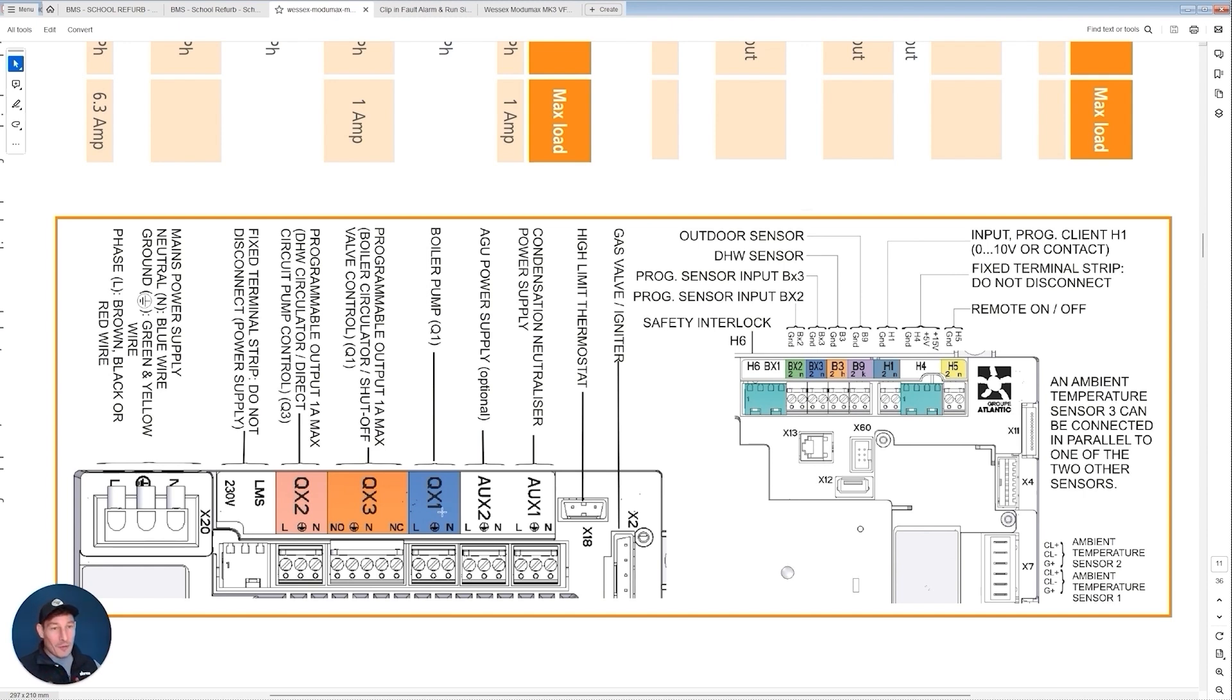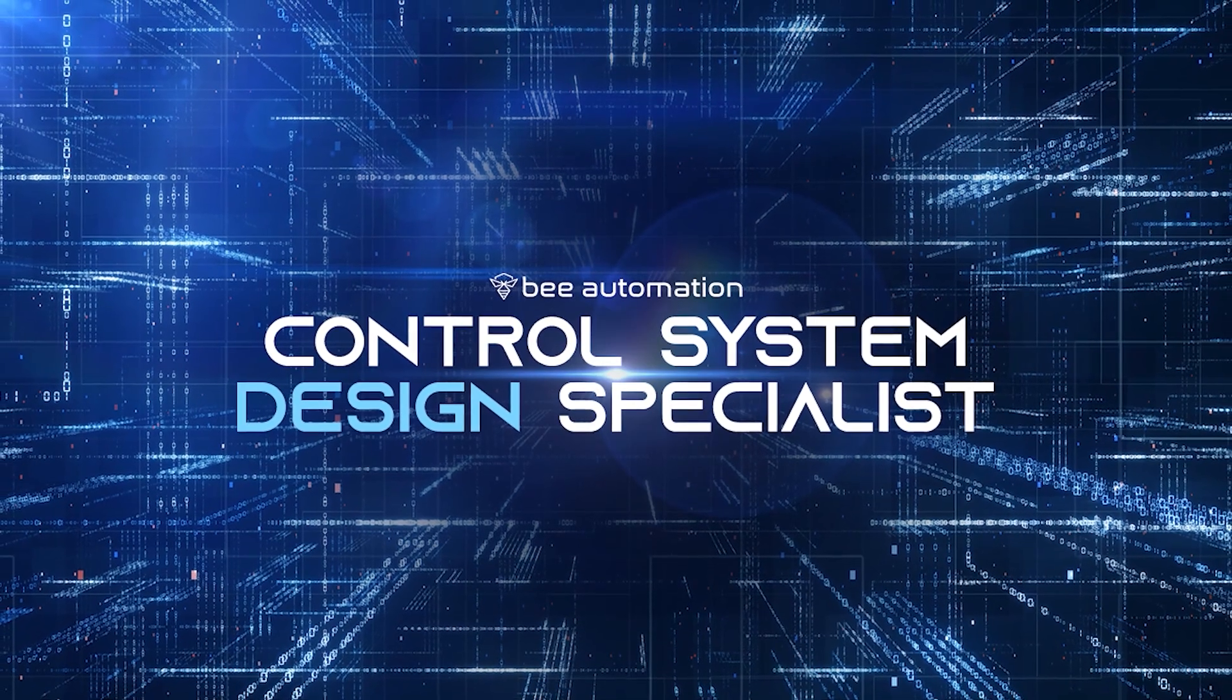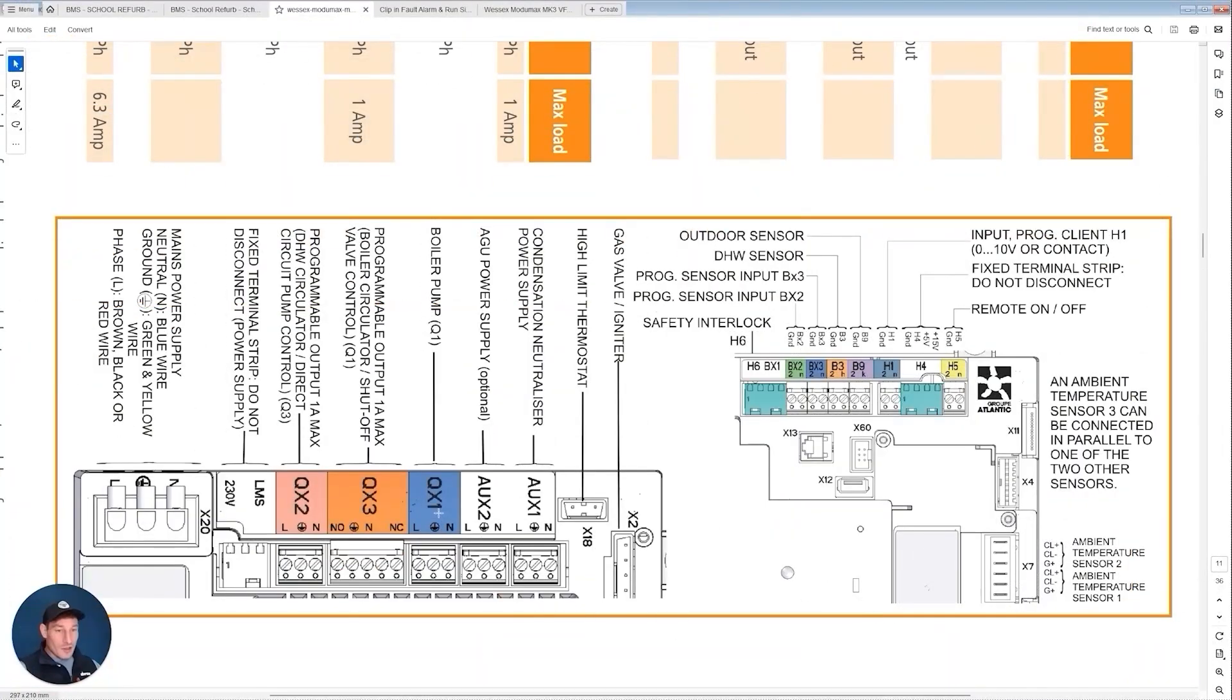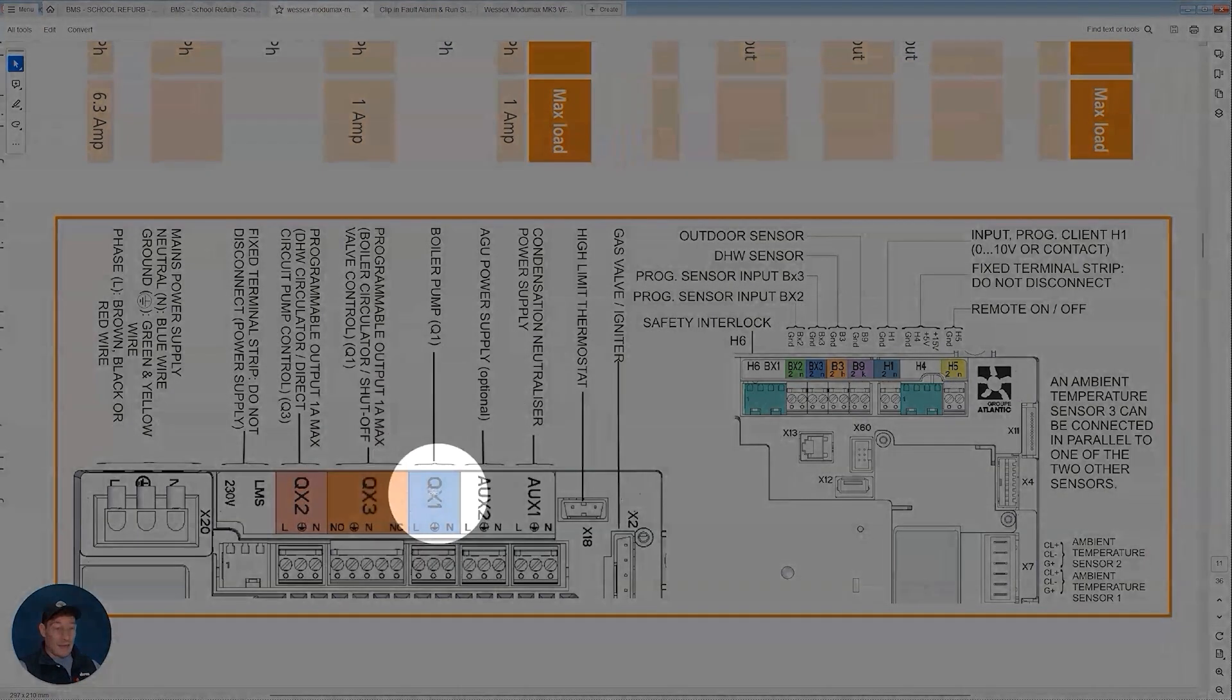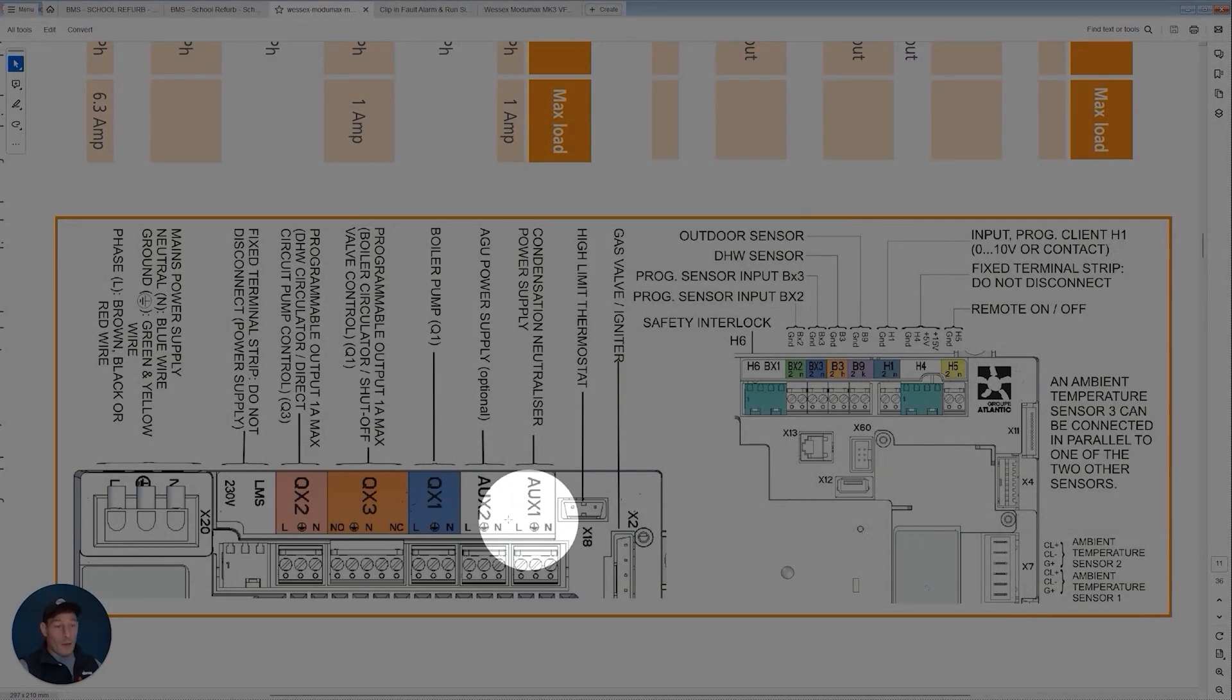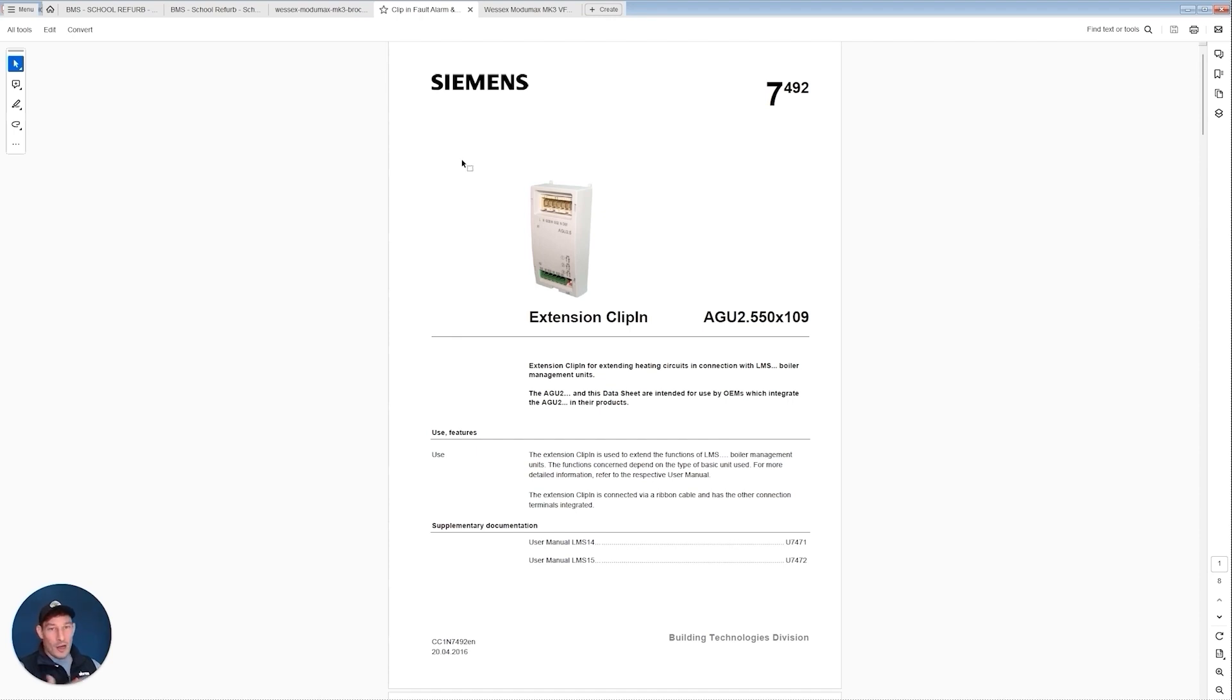We go into the details of what I'm about to go through in Control System Design Specialist, but just to quickly give you a brief overview, I had to spend a lot of time back and forth to tech support to work out how we were going to capture those outputs because they're not supplied natively by this boiler. What needs to be provided for this boiler to give us those outputs is one of these Siemens Extension ClipIn module. This is kind of like an OEM module that multiple boiler manufacturers use to enable them to give that signal.